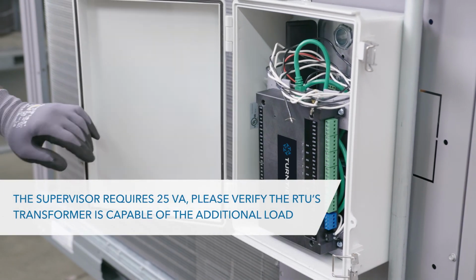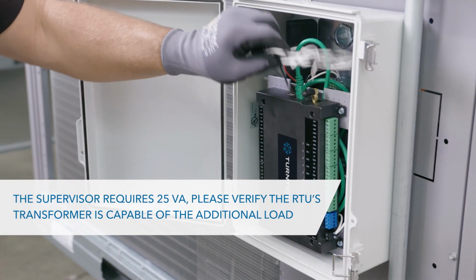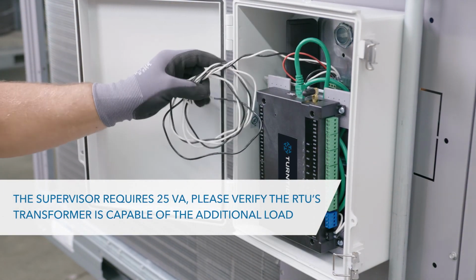The supervisor requires 25 VA. Please verify the RTU's transformer is capable of the additional load. If not, you may need to install a new transformer.